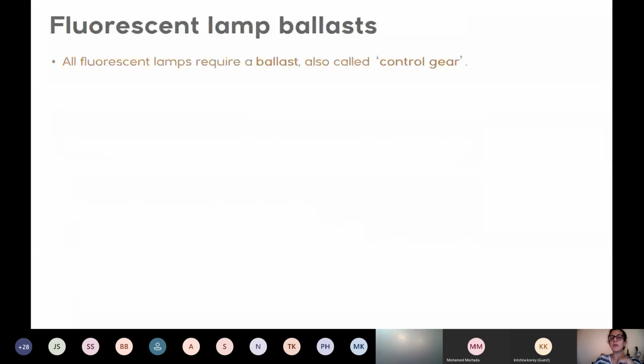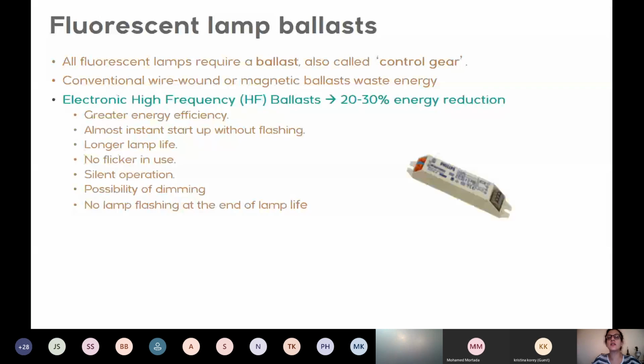Something else to keep in mind for energy efficiency is that all fluorescent lamps require a ballast, also called a starter or control gear. The conventional type is wire-wound, or a magnetic ballast. If you've had fluorescent lamps in some old houses, you remember we used to call them 'lampa battariya,' and they used to flicker a lot and make a buzzing sound. Both the flicker and the buzzing are caused by the magnetic ballast.